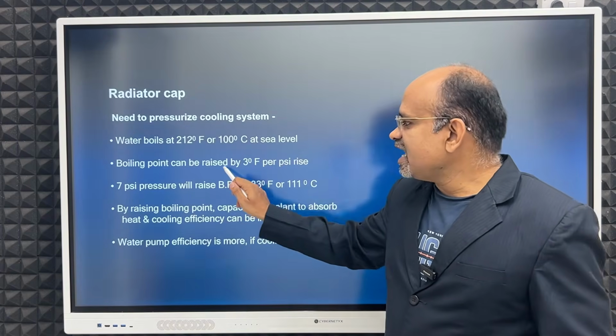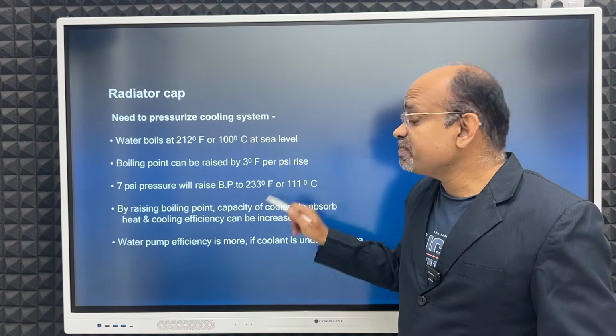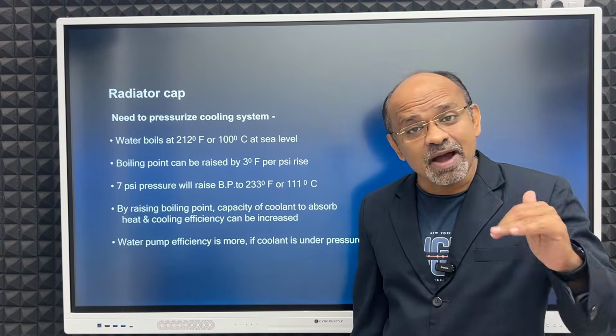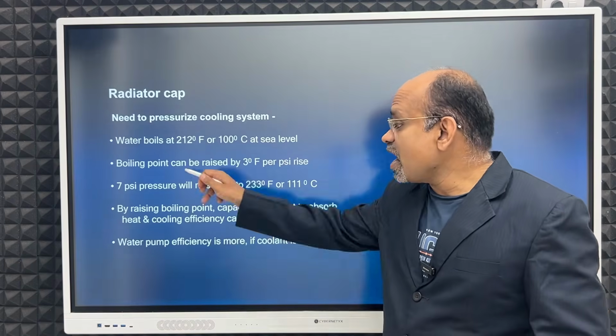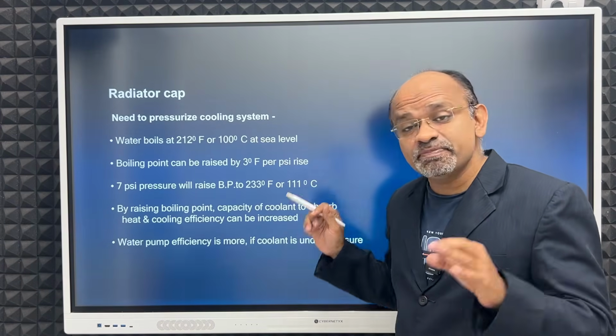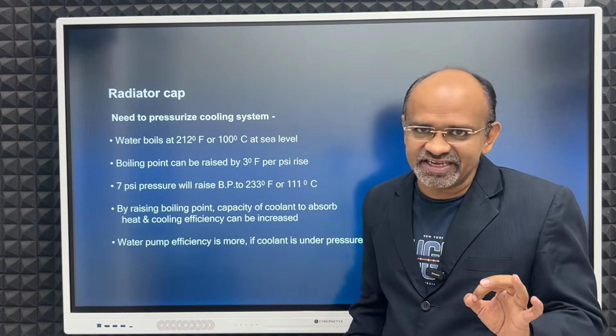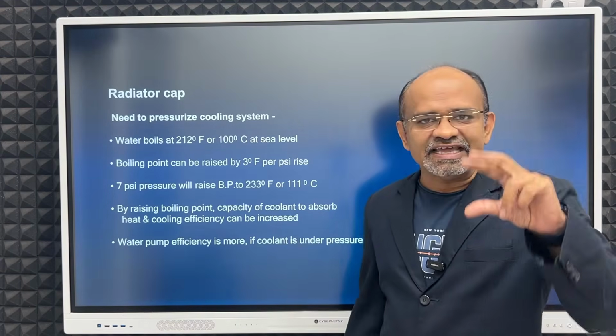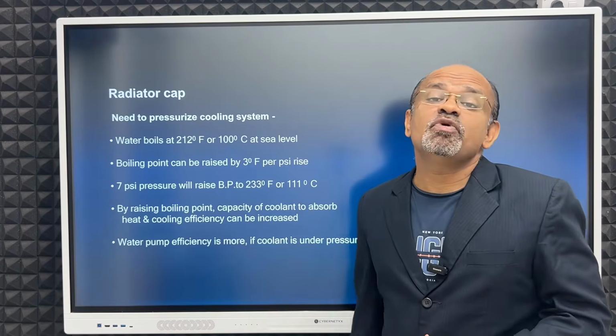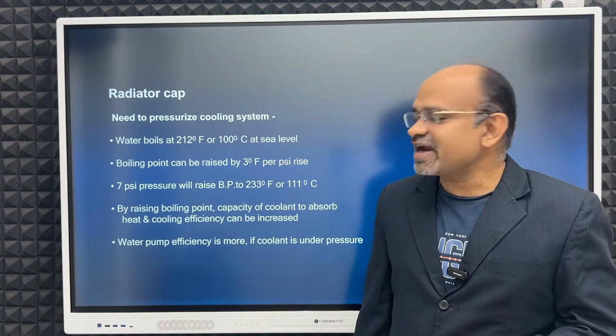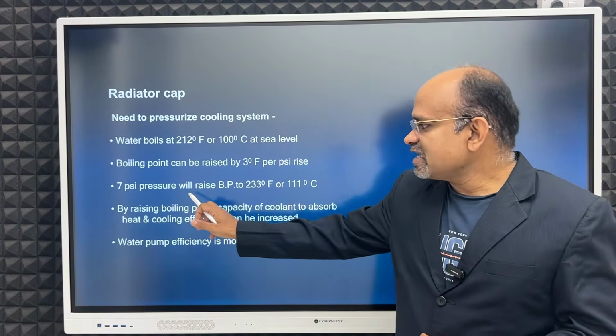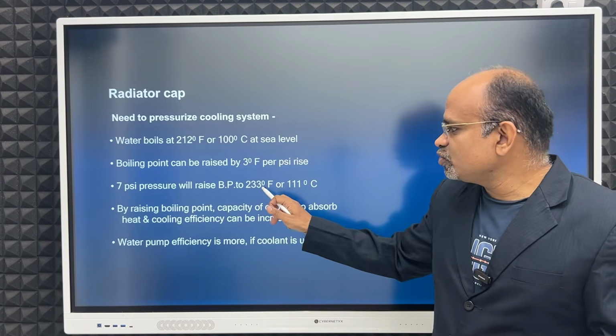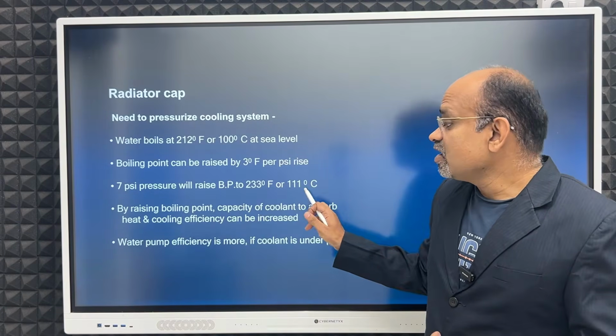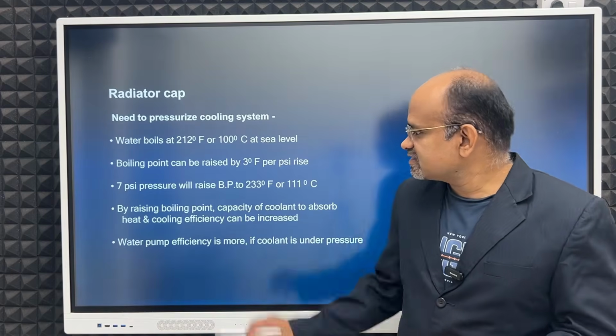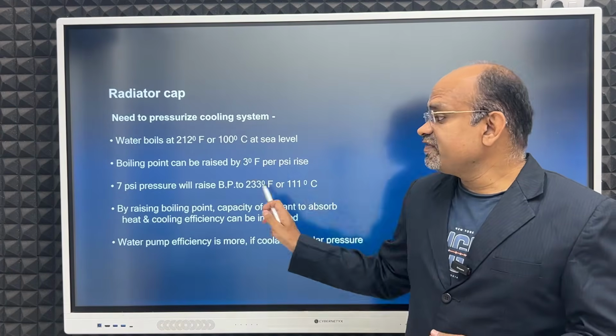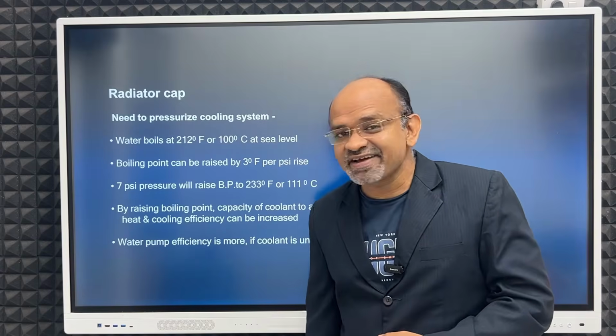So boiling point can be raised by 3 degree Fahrenheit per psi rise. If pressure goes up, boiling point will also go up by 3 degree Fahrenheit per psi. Psi is a pressure unit. Okay, every psi increase in pressure, it will increase the boiling point by 3 degree Fahrenheit. Then 7 psi pressure will raise boiling point to 233 degree Fahrenheit or 111 degrees Celsius. 11 degree difference, 7 psi pressure increase.